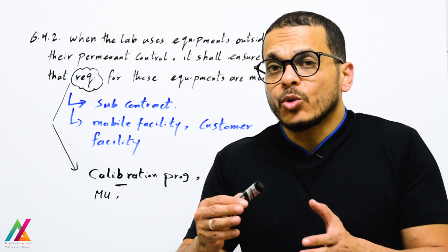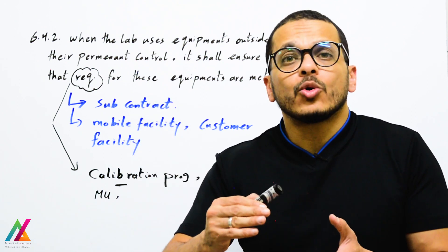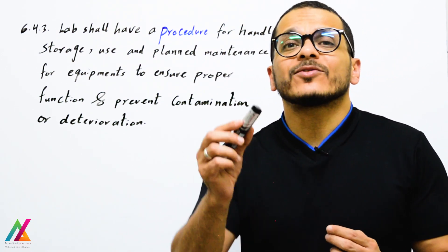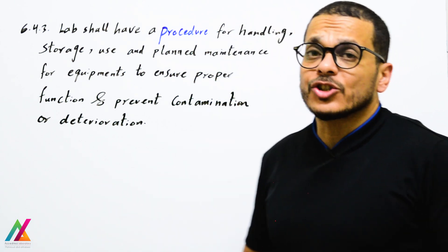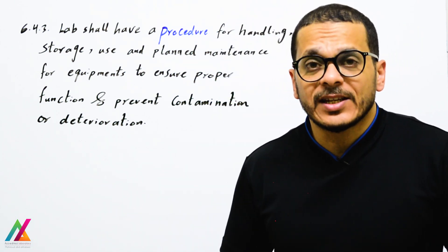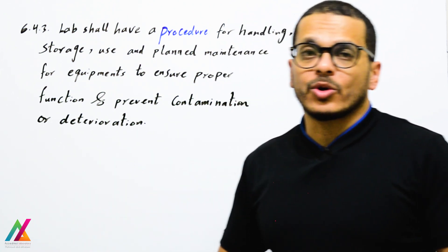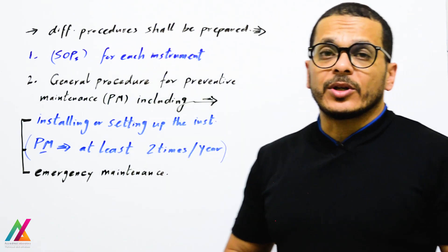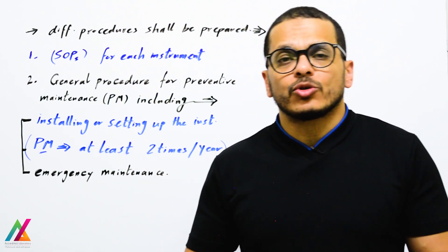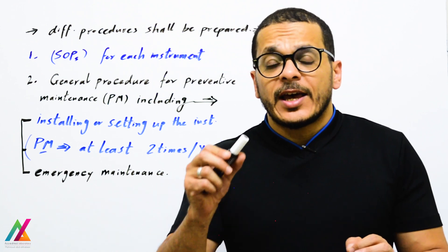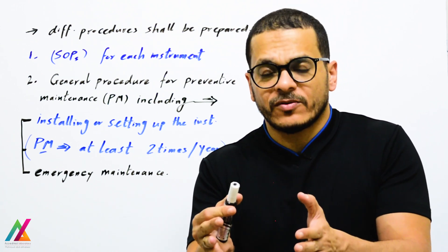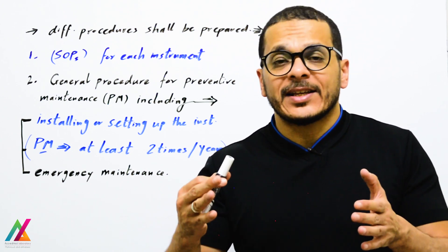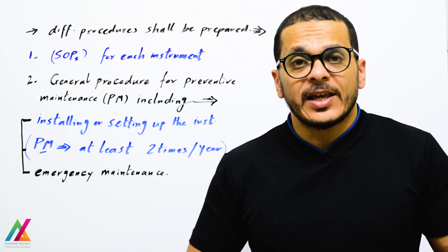The lab shall have a procedure for handling, storage, use, and planned maintenance of equipment to ensure proper function and prevent contamination or deterioration. Based on clause 6.4.3, different procedures shall be prepared. First, a standard operating procedure (SOP) for each instrument in the lab, including how to run the instrument, how to prepare a sequence, how to get results, how to calibrate it, and how to perform preventive maintenance by the analyst and engineer.